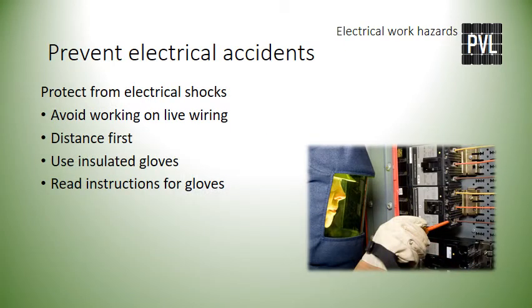Protect from electrical shocks. Distance is the best protection from shock, but insulated gloves can help protect against shock if you must work on live wiring. Insulated gloves range in voltage protection, so ensure you select the correct pair. Remember to read the user's instructions thoroughly before using insulated gloves — they require a high degree of care when using and when storing. Ensure you properly test your insulated gloves before each use and regularly inspect them per the manufacturer's recommendation.